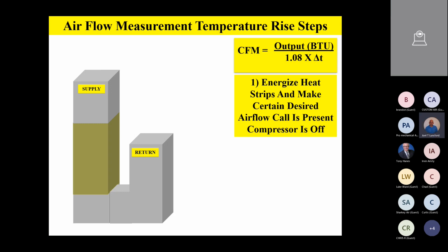We're going to energize the heat strips and make certain that the airflow call we want is present, and the compressor is off. This is huge. You don't want the compressor on. So you're going to shut the disconnect off outside. You're going to select the speed tap that you want to test on the air handler. You're going to energize the heat strips, and you're going to run the fan with the heat strips energized and the compressor off outside. Step number one.